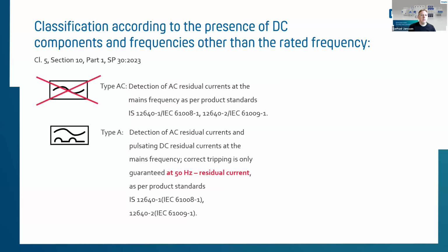So the type AC is not state of the art anymore. In Germany, it's not allowed to use it anymore since 1982. In a lot of different countries as well, it's banned, but it's still existing in a lot of European countries as well, but it's not the best detection anymore. So type A should be the minimum requirement on the market to have at least a bit more protection.